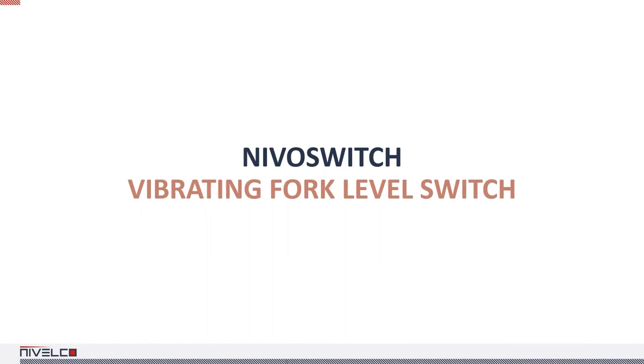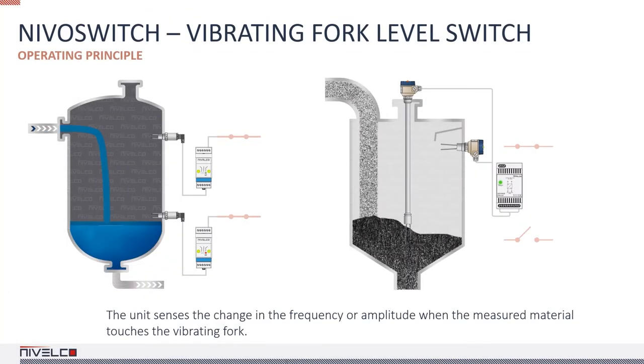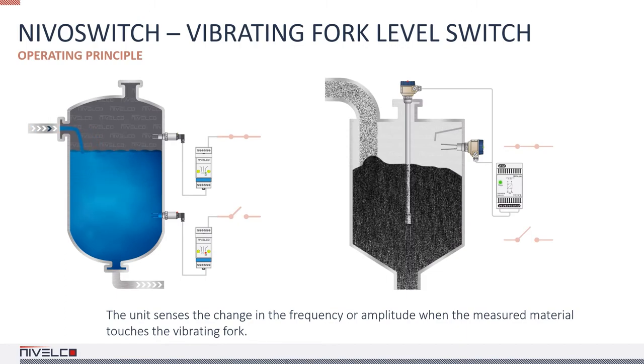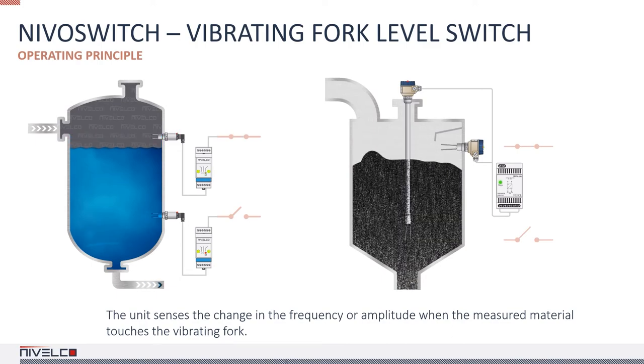NIVOswitch vibrating fork level switches are suitable for liquids, granular solids, and powders. The operating principle involves an electronic circuit that keeps a fork probe in an excited state by inducing vibration in it. When the medium touches the fork, the vibration changes or stops. As soon as the medium drops to a level where it no longer touches the fork, the probe starts to vibrate freely again. The unit senses the change in vibration and sends out a signal after a pre-configured delay.